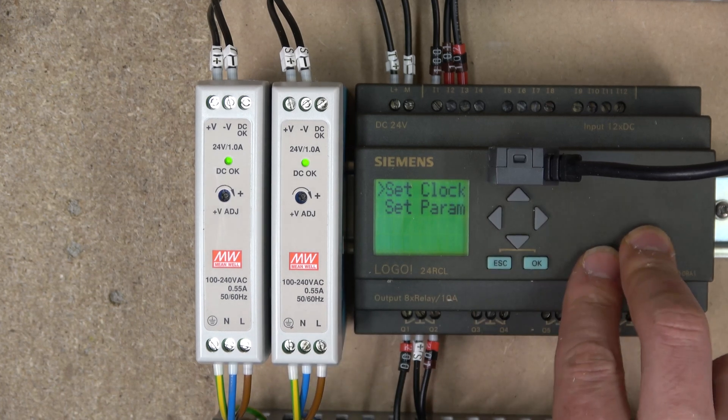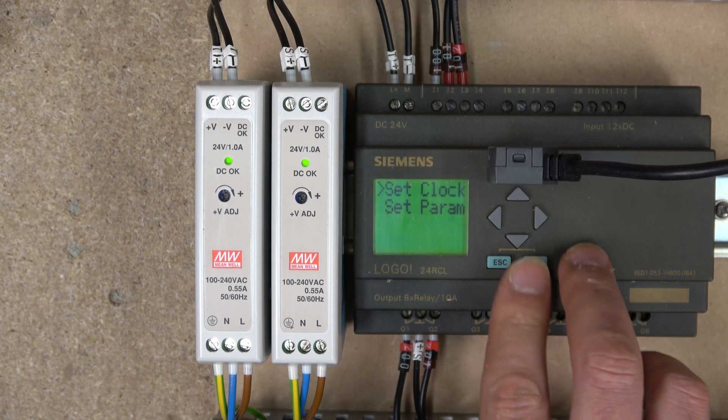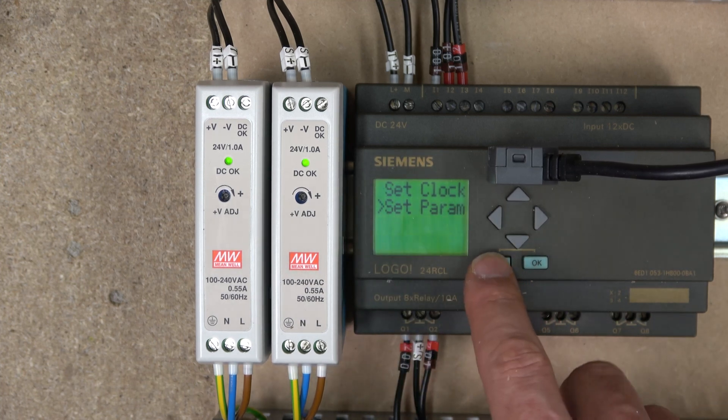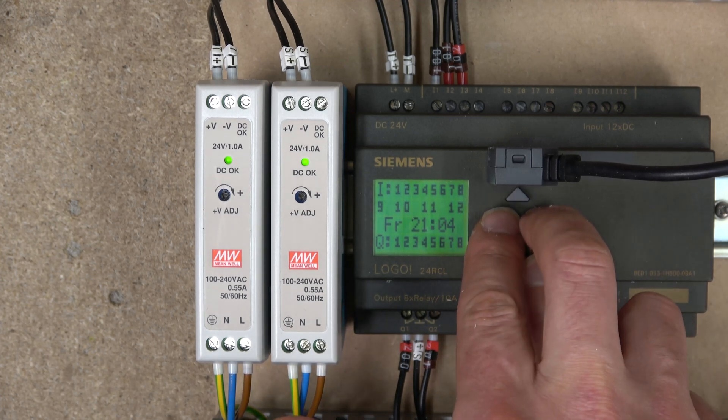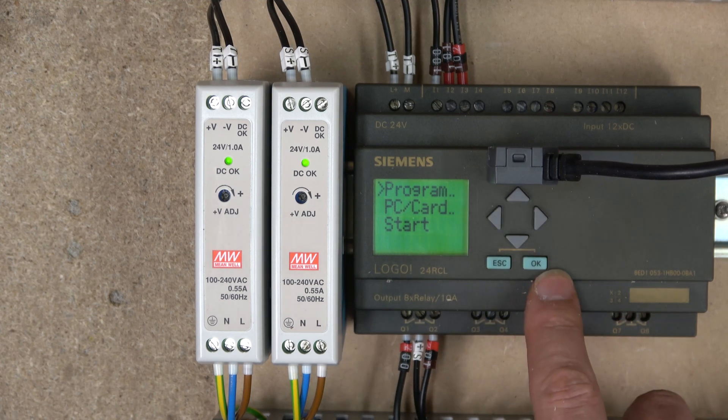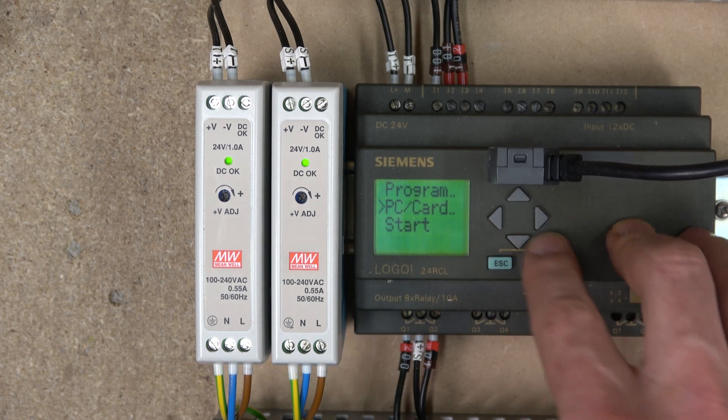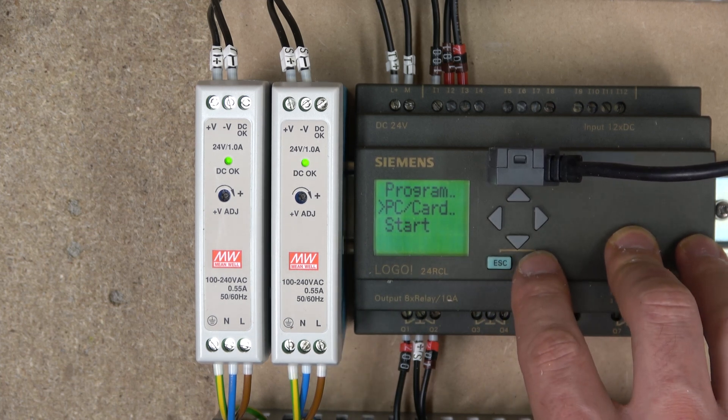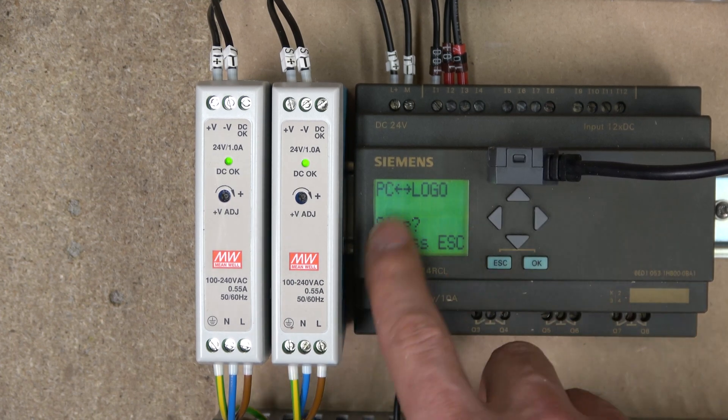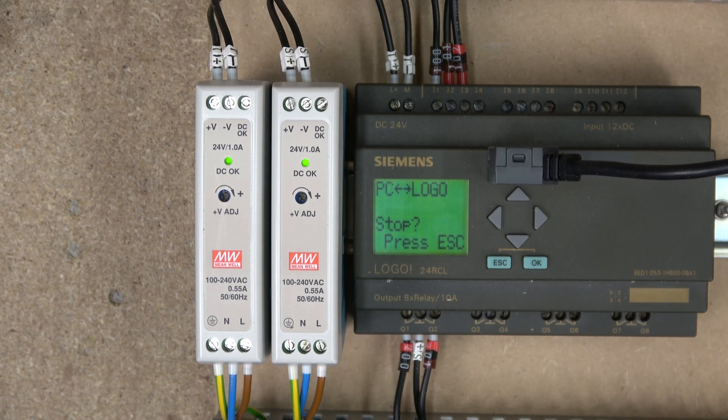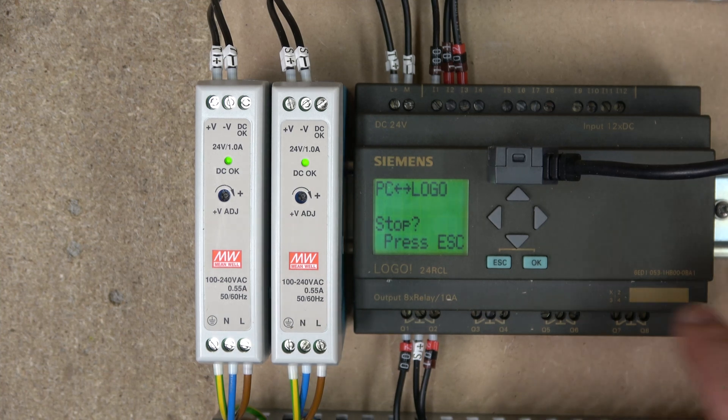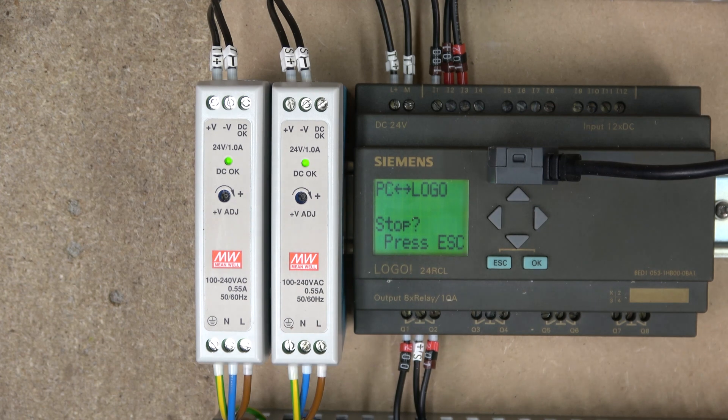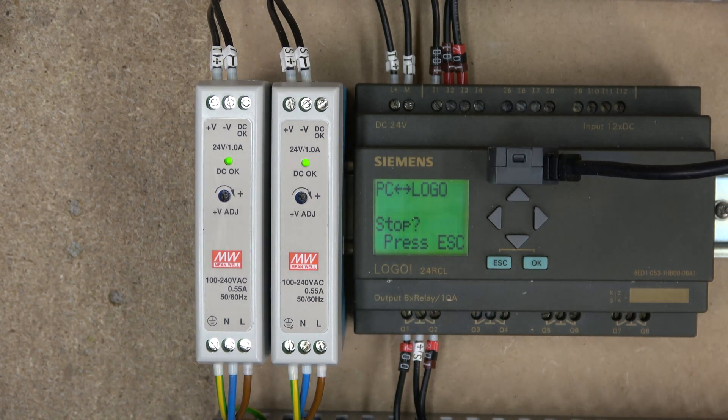From there on, you need to set your controller into transfer mode. There's a couple of ways to do it. By clicking ESC and OK together you will get to this menu where you can set your clock and parameters. By holding OK and clicking both buttons sideways together, you'll enter the programming windows. We need to go to PC/Logo and press OK. As soon as it is in this mode, we will be able to read what's inside the controller and load the program into the controller. You do need to make sure you are in this window, otherwise the transfer will not work.